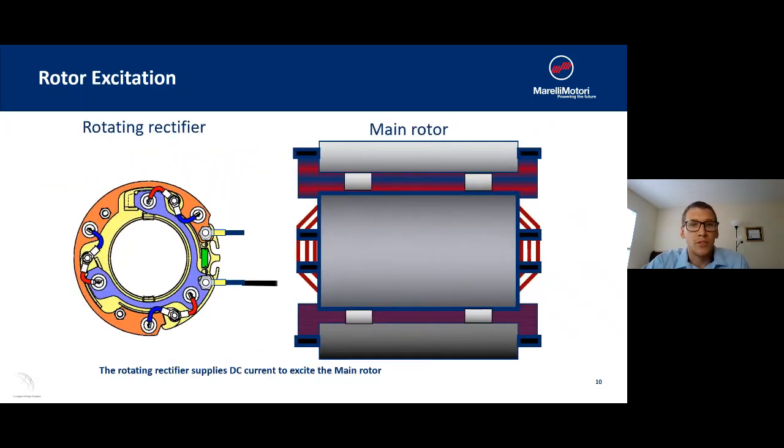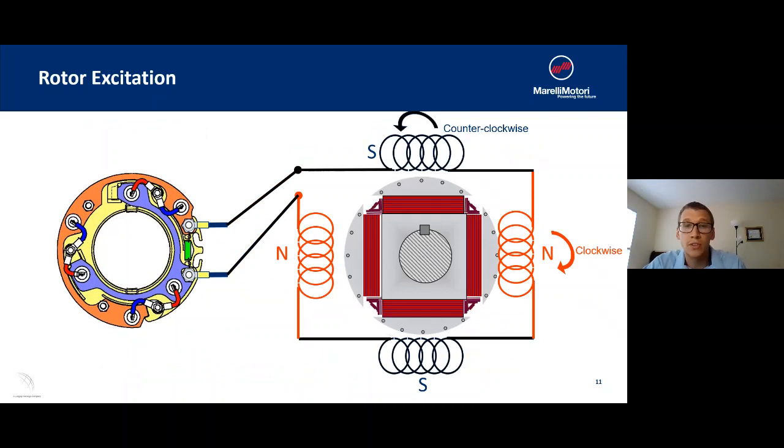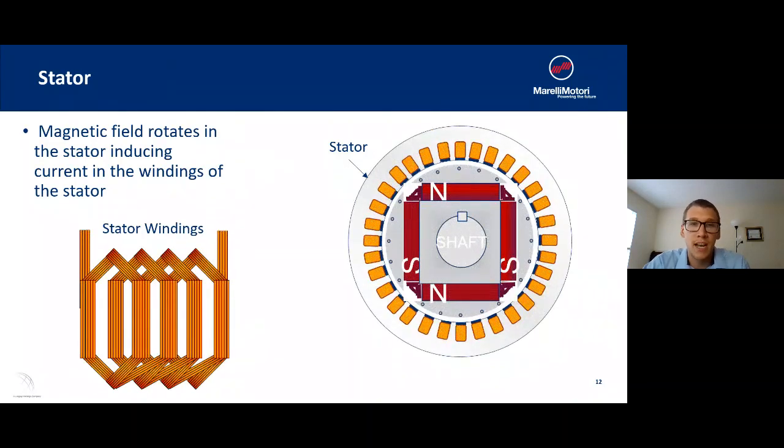How this really works to create the magnetic field is the rotating rectifier is going to inject that DC current into the main rotor, and then the main rotor is wound very similar to the exciter stator where you have sets of clockwise or counterclockwise windings which create a north or a south pole. What we're looking at here is an example of a four pole main rotor which is what our standard stock generators keep. The main rotor then will rotate inside of the main stator. The main stator is also made up of a few sets of windings and as this magnetic field rotates inside the stator it's going to induce the current into the windings of the stator which is where you're going to get your output.